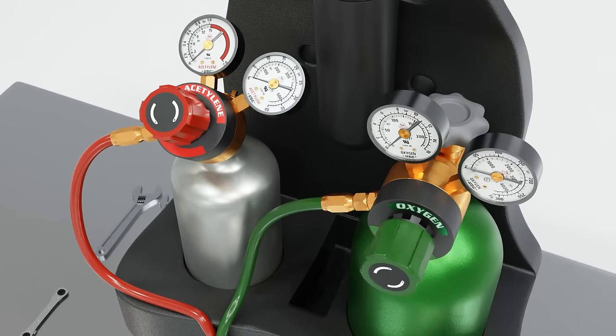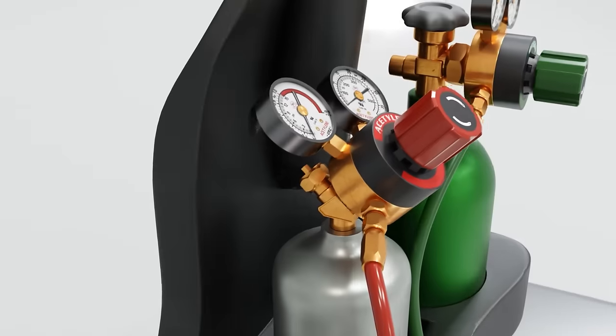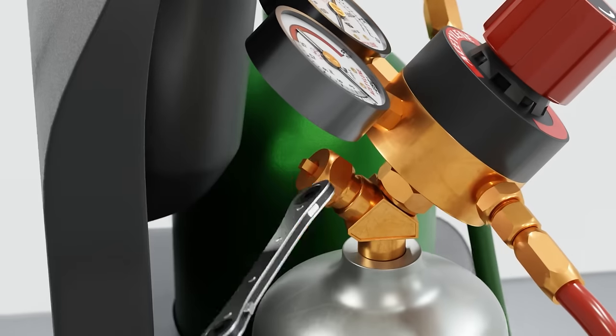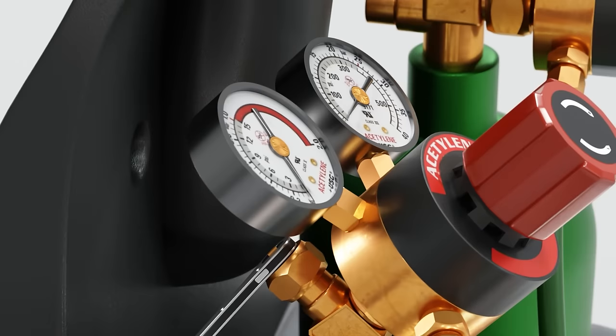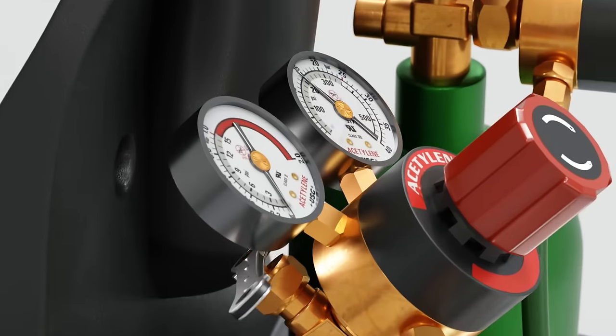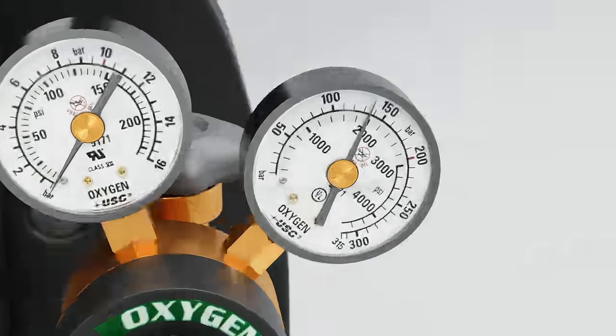Next, turn your regulator adjustments counterclockwise, closing them off completely. Then open your tanks. Use a refrigeration wrench for your acetylene tank. Do not use a crescent wrench or channel locks. Now open your oxygen tank.